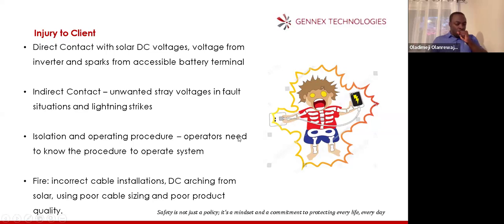We need to educate our clients. Because for instance, let's assume you have a full inverter system, and if the client is not using the batteryless or battery independent inverter, and the client just turns off the battery breaker, there is possibility that the inverter can go bad. Or let's say the charge controller also, if there is supply from the sun and you turn off the battery breaker, there is tendency that the system can go bad as well. So all these operating procedures that could cause harm need to be addressed and carefully communicated. You communicate this carefully to your clients.